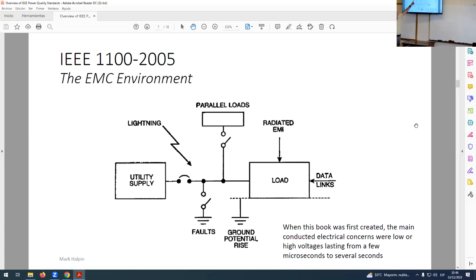Overvoltages associated with lightning or some kind of switching transient, we all understand that damages equipment. We have to manage that from a performance perspective. Faults, we all understand, when faults occur, produce sags, and sags low enough will disrupt equipment. Those were the two things the Emerald Book considered about the quality of the utility supply. But that's not what you came here today to hear about. We take that for granted.